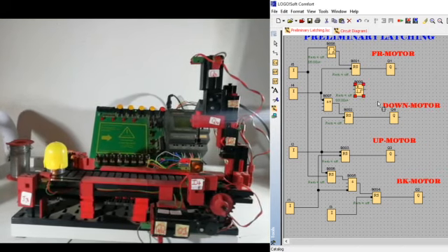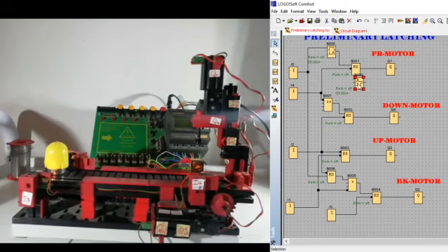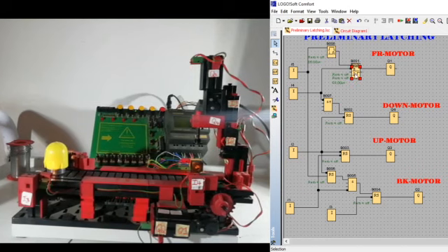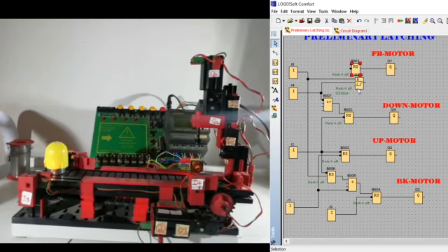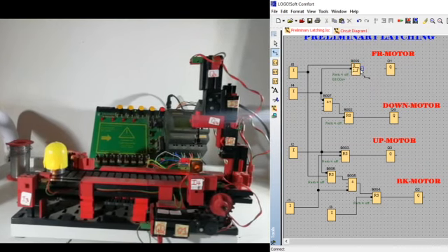Okay, perfect. So this retentive on delay will replace the latch here. Because the retentive on delay can memorize that we need to delay before we start the process, unlike using the on delay, and then you need to always invert wherever necessary.